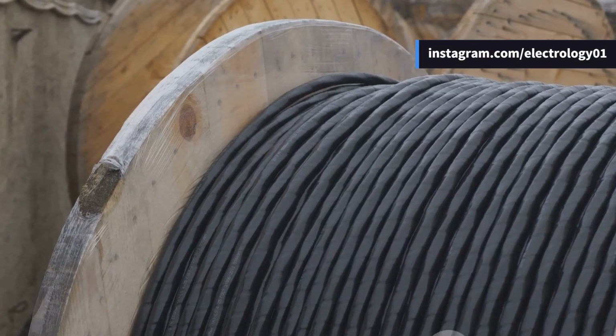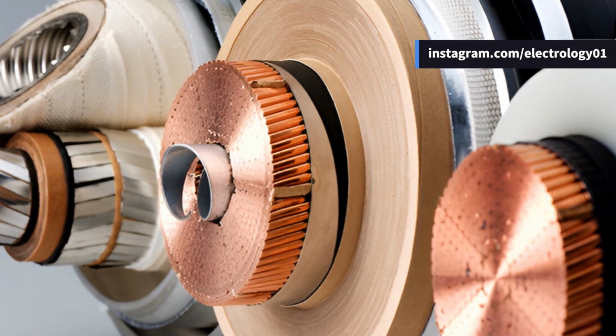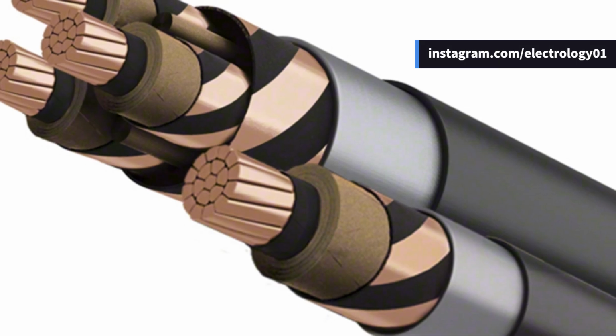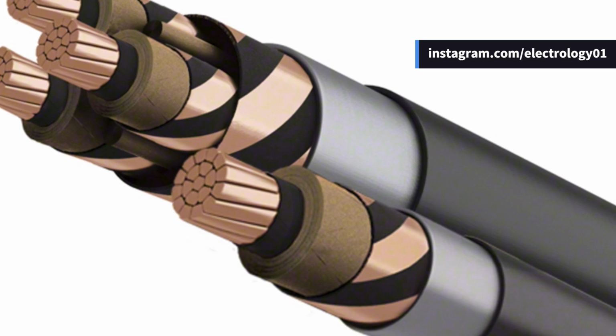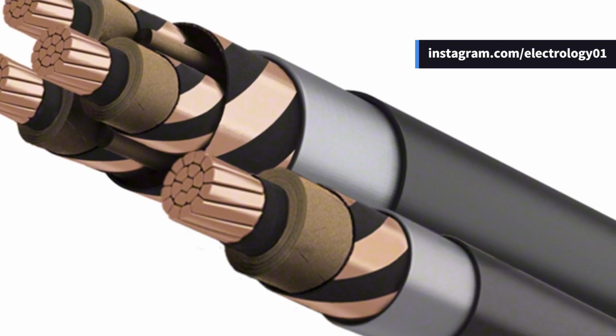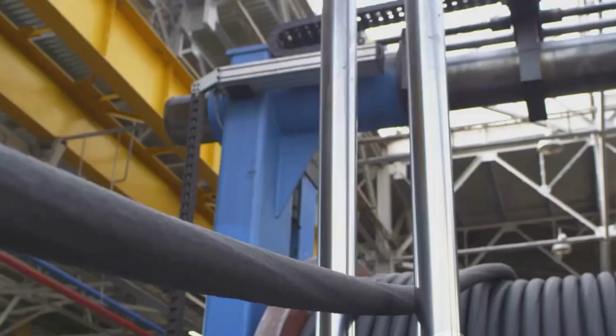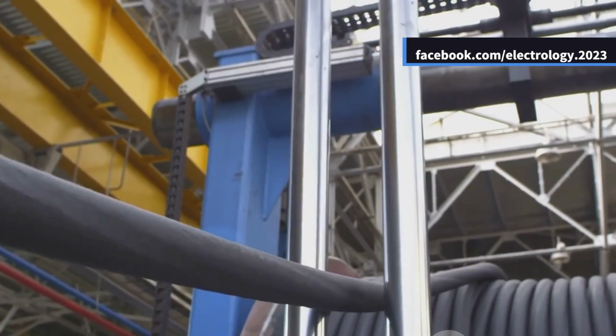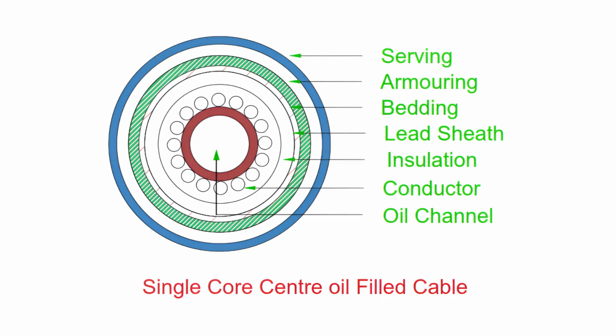So, solid cables are simple, but, you know, they do have their limitations. At higher voltages, the insulation might crack or form voids because of heat, and that can cause breakdowns. That's where pressure cables come into play. Oil-filled cables circulate oil under pressure to keep insulation layers compressed and avoid voids. These are used up to 230 kilovolts and help prevent electrical faults by filling gaps.